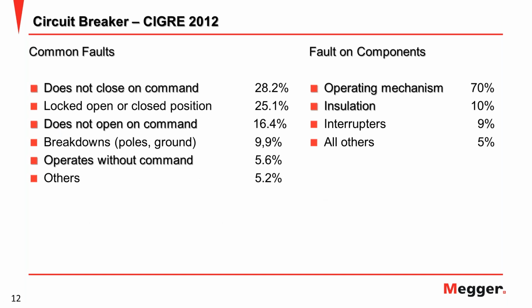Yeah, this is information that maybe can be used to consider why we should do maintenance on your breaker. Based on the CIGRE research 2012, for the common faults, the highest percentage, 28.2%, is does not close on command, followed by lock in open or close position. It can be because of a mechanical issue, but it gives a big percentage. Number two, I think, is 25.1%, and then does not open on command, breakdown to ground, operate without command, and other. So actually, this result is taken from medium voltage breakers and also high voltage circuit breakers.